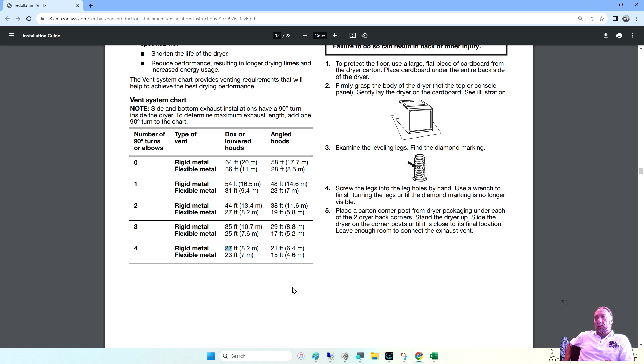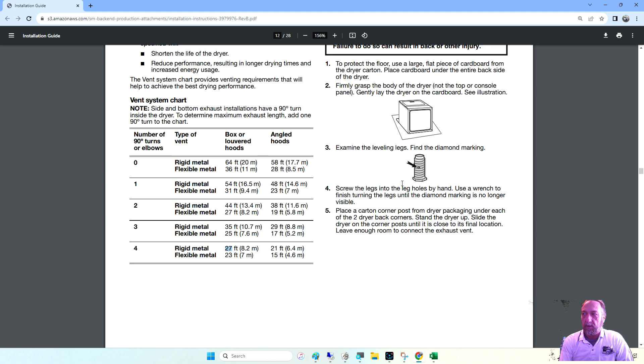But again, I'm not trying to teach you right now how to install a dryer. I'm trying to tell you guys, if you want to be a good technician, you can't just learn to read wiring diagrams and say, well, I got this. Because what if it's not an electrical problem? What if it's an installation problem? What if the manufacturer put the wrong pulley on the motor? You have to start to think, when you go into a house, yes, we approach everything as an electrical problem when we first get there. We turn it on, we want to see what's running and what's not running, and then we make our plan of attack on the machine. But you guys need to make a plan of attack on what you need to learn in order to be able to troubleshoot these things.